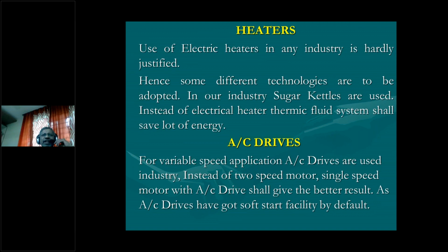Now, when we move to AC drives, that is variable speed drives used in the industry, I came across some applications particularly in old machines. I came across many machines having two-speed motors. Technical words we say double star delta motors, two pole motor and four pole motor. There are six terminals, three upper, three lower side. If you give three wires to the upper terminal, your motor will be a high speed motor, two pole.